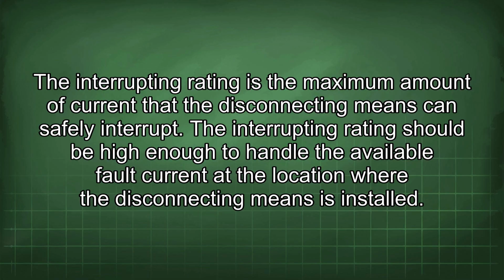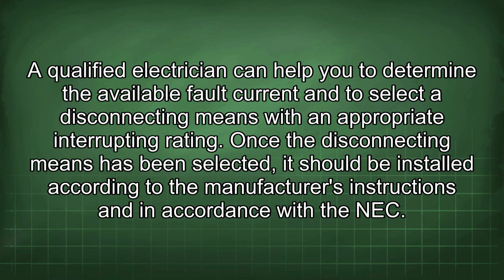The interrupting rating should be high enough to handle the available fault current at the location where the disconnecting means is installed. A qualified electrician can help you to determine the available fault current and to select a disconnecting means with an appropriate interrupting rating.